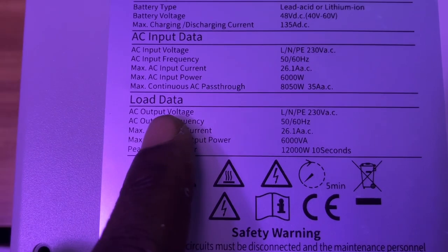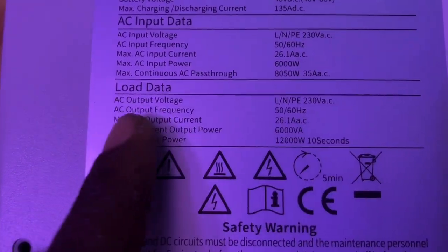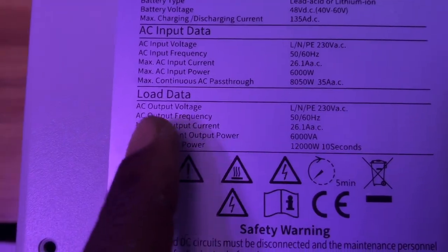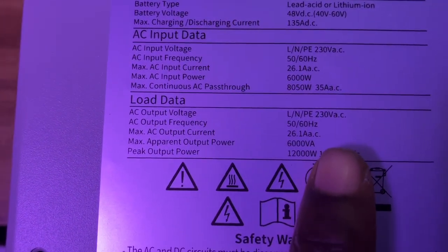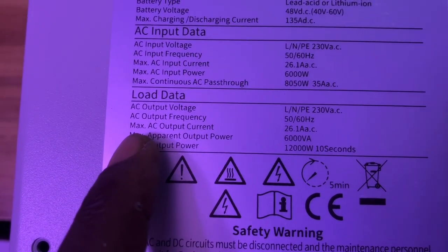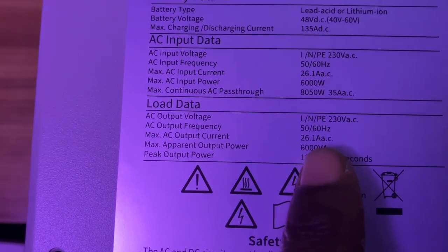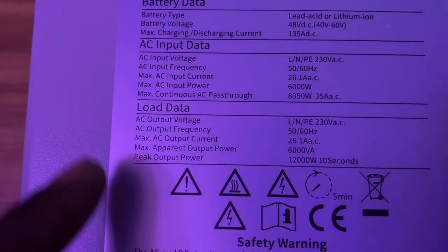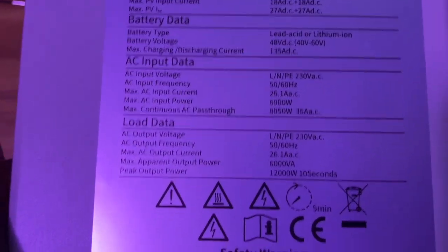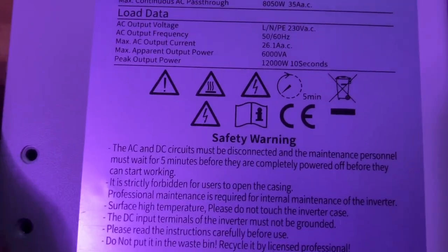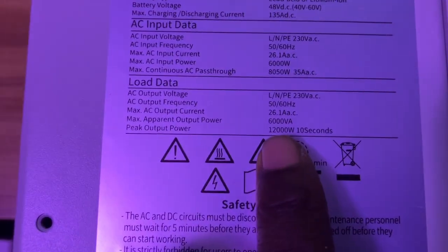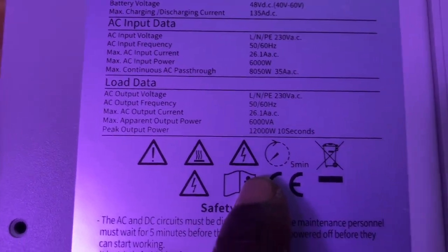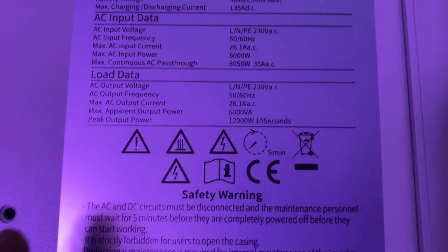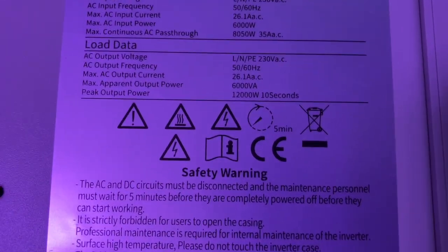So we have AC output, which is 230, frequency is the same as the input, output current is 26, and we also have the power, which is 6,000 VA. So this inverter has a power factor of 1, and the peak output is 2 times the rated capacity, and it can do this for 10 seconds.